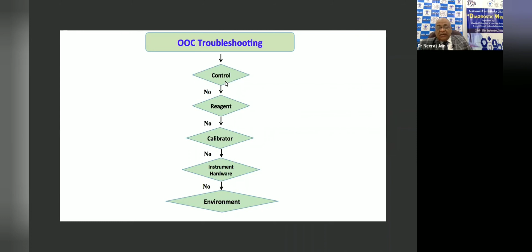The person who is performing all this activity may not be trained to carry out all these activities. For control, use the correct material. It should not be expired. It is stored properly. If you are preparing aliquots, you are preparing them in tubes of appropriate size, neither too large nor too small. Then these are reconstituted properly, and when you are bringing those to room temperature, you are running them promptly so that some material is not evaporated. If it is evaporated, you may get a higher result because of more concentration, or some water droplet may fall in the control material, and you may get a lower value.